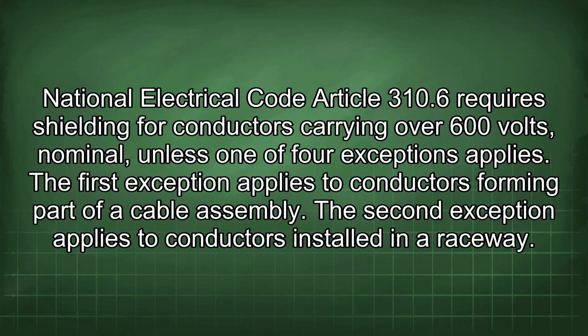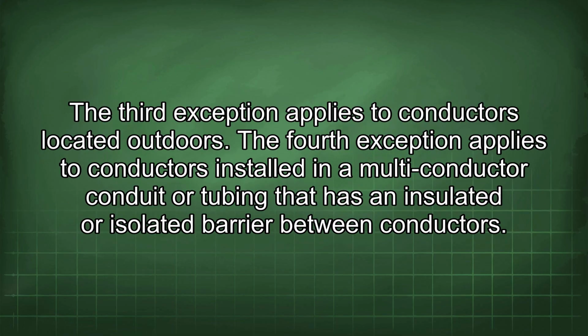National Electrical Code Article 310.6 requires shielding for conductors carrying over 600 volts, nominal, unless one of four exceptions applies. The first exception applies to conductors forming part of a cable assembly. The second exception applies to conductors installed in a raceway. The third exception applies to conductors located outdoors.